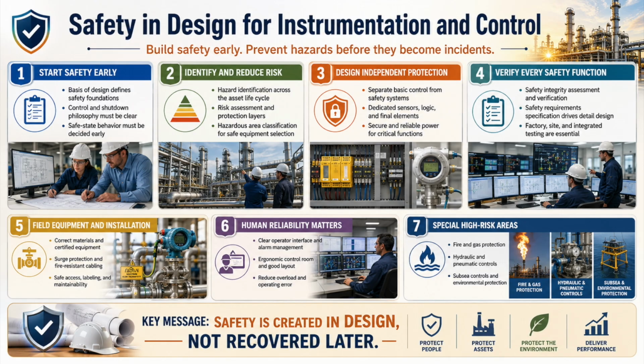Safety functions must remain independent from basic process control functions. Integration may improve visibility, but it must not create common failure paths. Safety sensors should use separate process connections. Safety wiring, junction boxes, input channels, output channels, logic, and final elements should be segregated wherever independence is claimed. Configuration access must be controlled so that a routine control change cannot silently weaken a protective function.